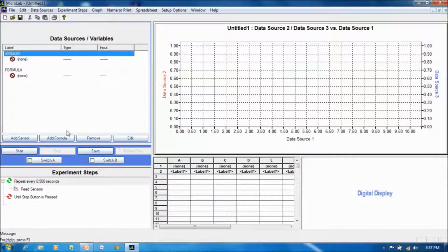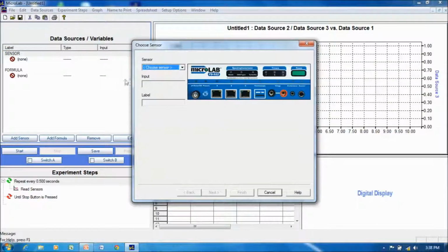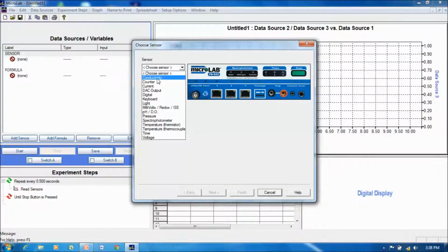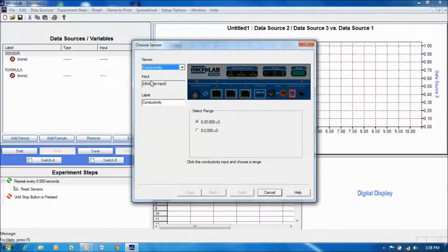And we're just going to add the conductivity sensor. So we'll start in the upper left-hand window. We'll add a sensor. We'll go to the drop-down menu and choose conductivity. The next thing is to choose the input. We have to confirm that we have it plugged in to the conductance jack, and we're going to select 0 to 20,000 microsiemens for the range of the sensor.